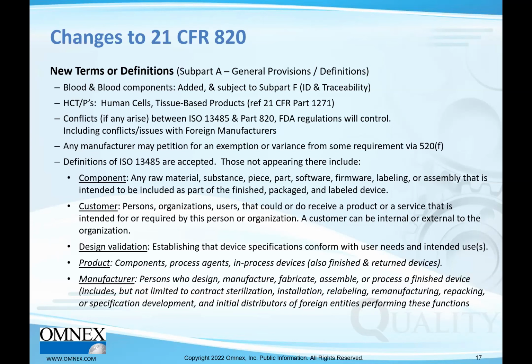Design validation. Establishing that device specifications conform with user needs and intended use. The difference between a design validation, a process validation, or design verification is intended use. Verification is to specs, validation is to intended use. Product and manufacturer, both of these are in 13485. But the rule or the definition for US purposes is the definition we have here. Components, process agents, in-process devices, also finished and returned devices. Manufacturers are persons who design, manufacture, fabricate, assemble, or process a finished device, and it includes but is not limited to contract manufacturers working for you, and I'm not going to read all of that.